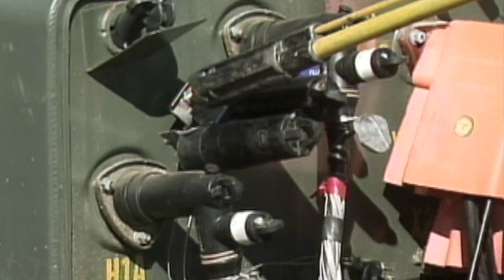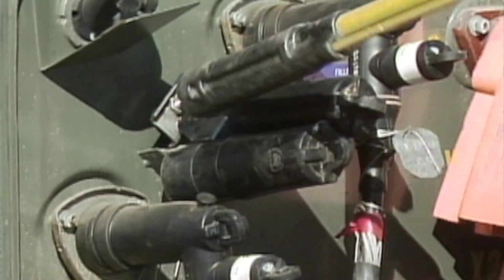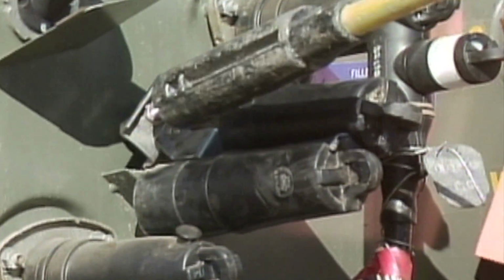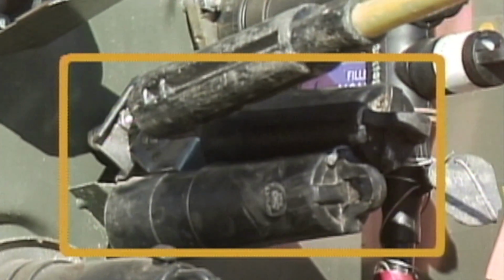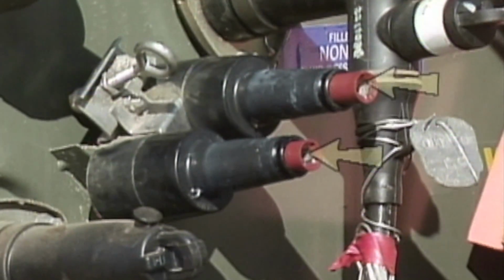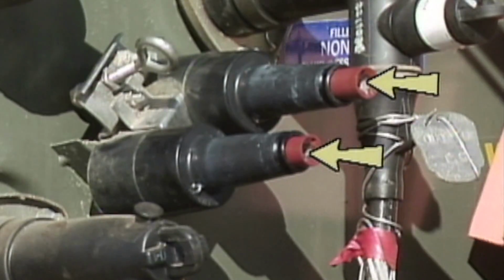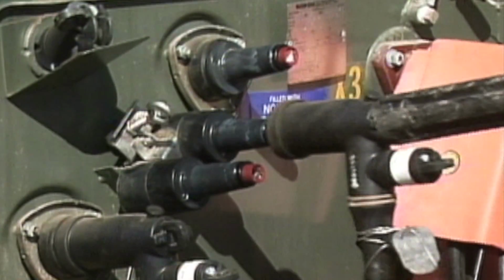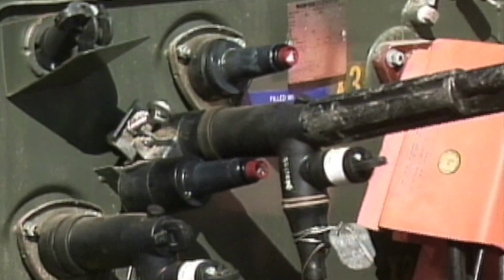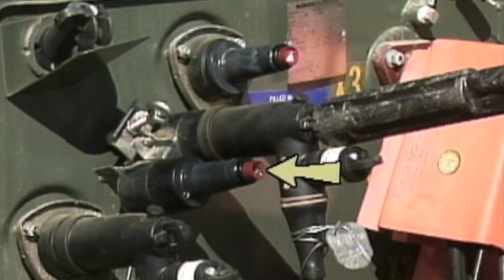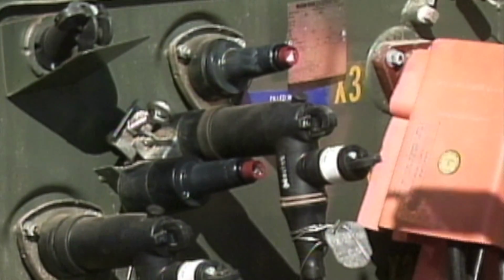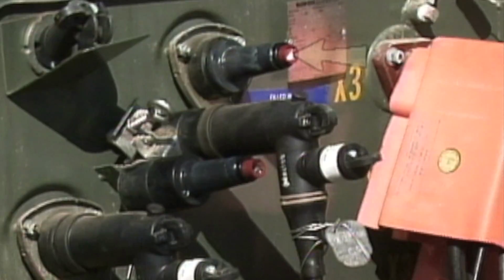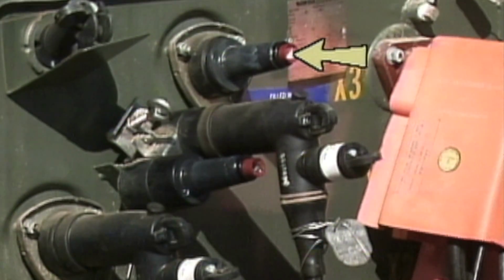Therefore, the workman needs to place one end of the cable he wants to test on a feed-through bushing. A feed-through bushing is a device that provides two electrically connected bushings. With the cable on one position of the feed-through bushing, he can test the cable's potential at the other position. He can also check the operation of the phasing tool on the open energized transformer bushing.